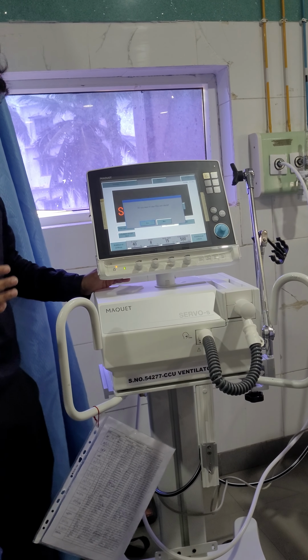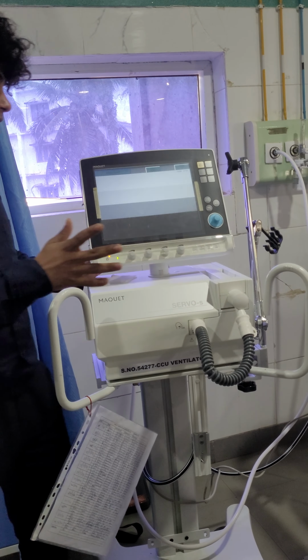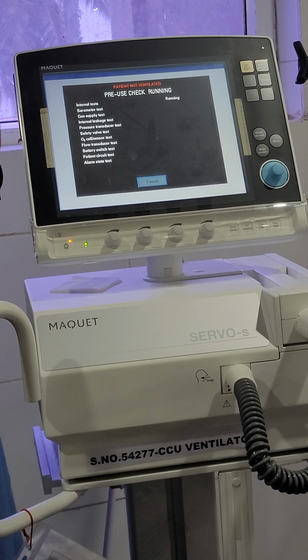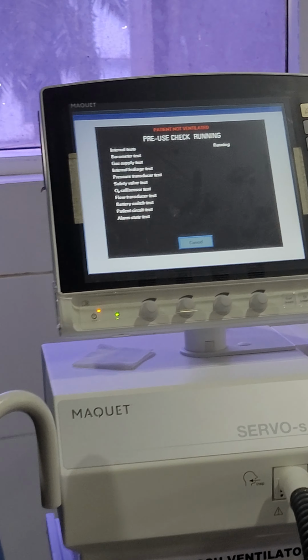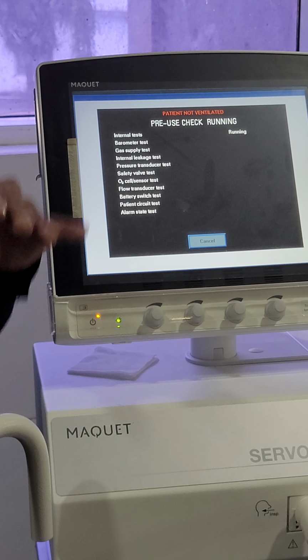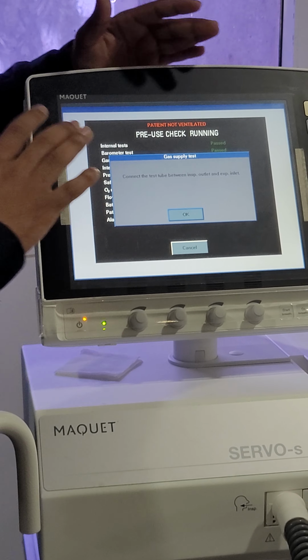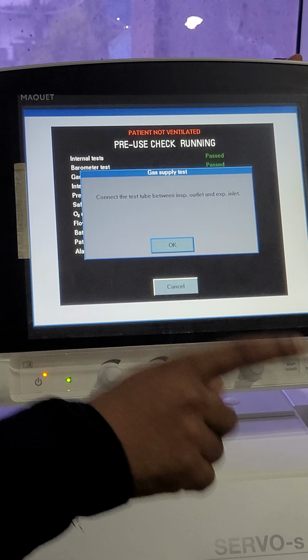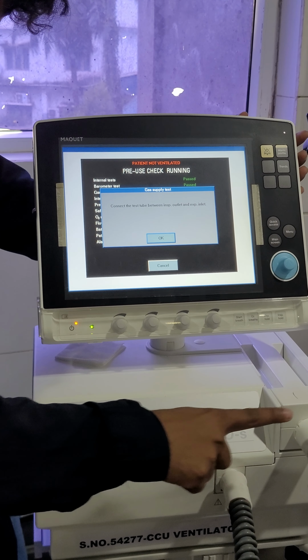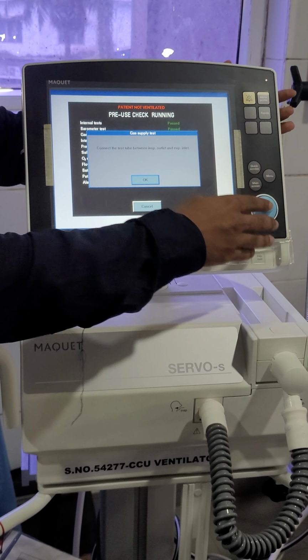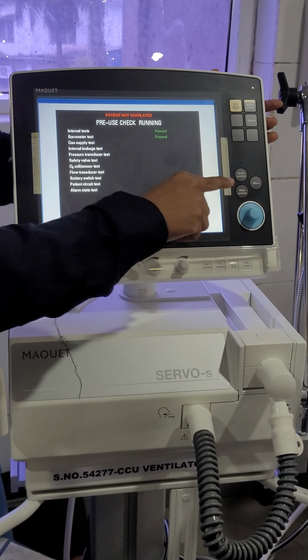We want to start the pre-use check. Yes, I want to start. Hardly, this test will take 3 minutes 30 seconds to 4 minutes, not more than that. Internal test: connect the test tube between inspiratory outlet and expiratory inlet, which I have already connected. This will be the expiratory side, this will be the inspiratory side, and I am pressing OK with this knob.